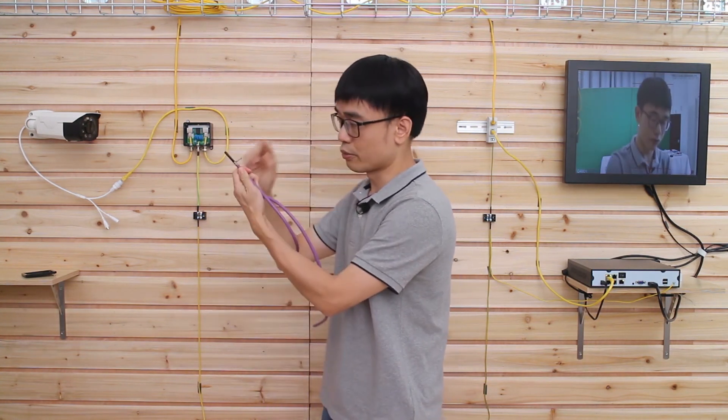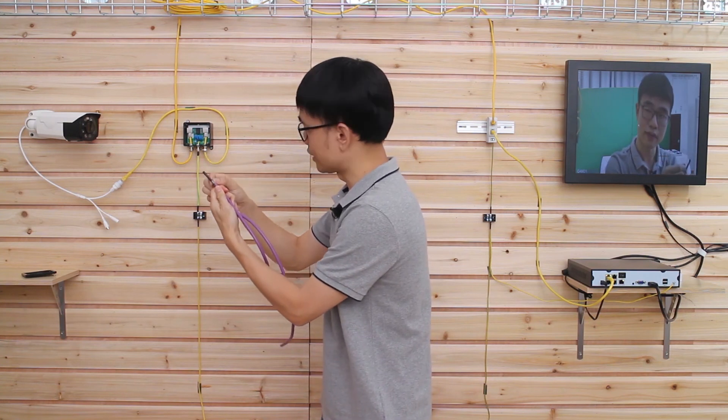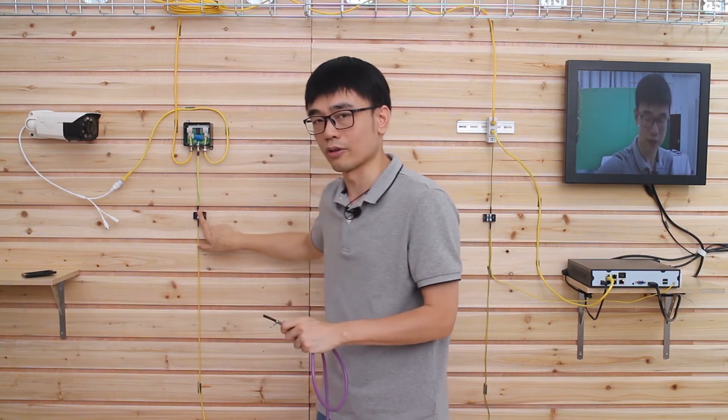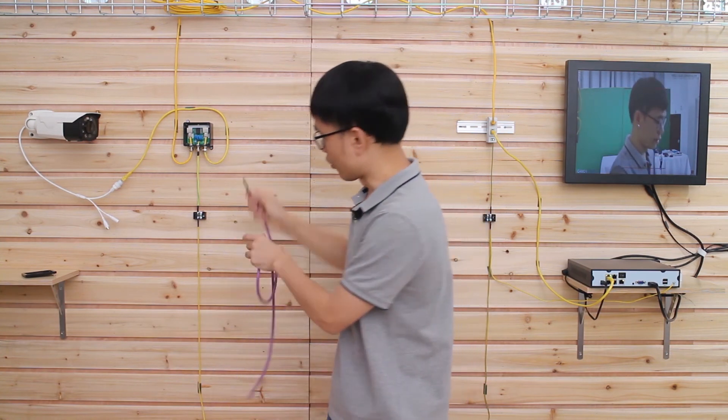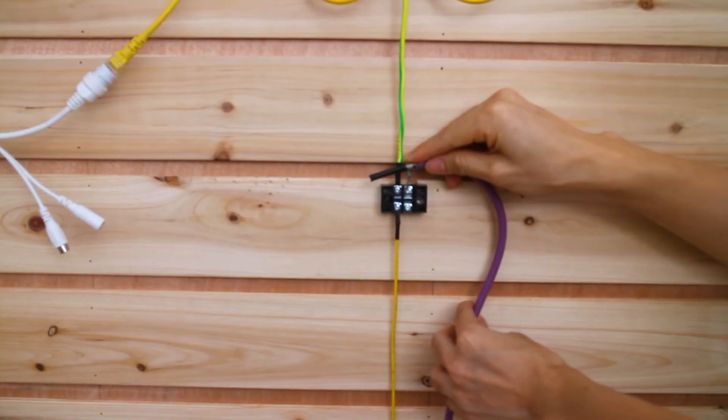So if you just connect the shield to the metal, it will not pass to this grounding spot, so it will not work. You need to ground the shield independently to here.